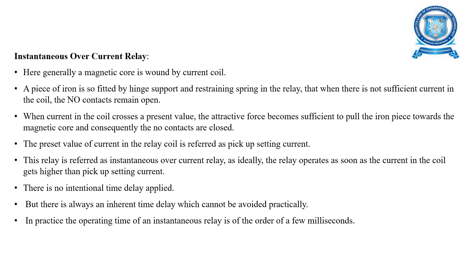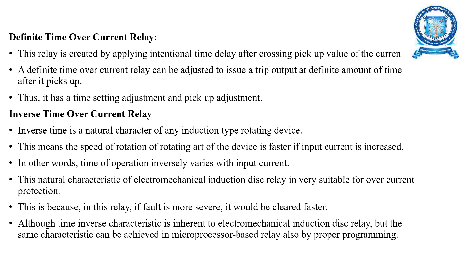This relay is referred to as an instantaneous overcurrent relay because ideally it operates as soon as the current in the coil gets higher than the pickup setting current. In practice, the operating time is in the order of a few milliseconds. Next is the definite time overcurrent relay, which is created by applying an intentional time delay after passing the pickup value of the current. It has both a time setting adjustment and a pickup adjustment.